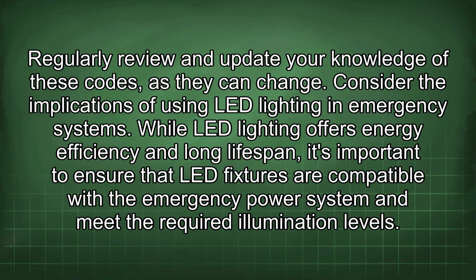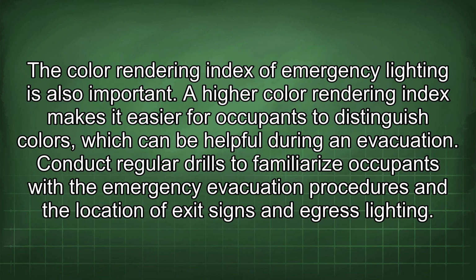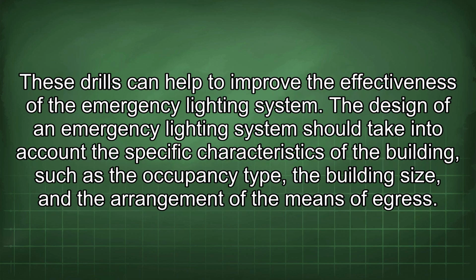Consider the implications of using LED lighting in emergency systems. While LED lighting offers energy efficiency and long lifespan, it's important to ensure that LED fixtures are compatible with the emergency power system and meet the required illumination levels. The color rendering index of emergency lighting is also important. A higher color rendering index makes it easier for occupants to distinguish colors, which can be helpful during an evacuation. Conduct regular drills to familiarize occupants with the emergency evacuation procedures and the location of exit signs and egress lighting. These drills can help to improve the effectiveness of the emergency lighting system.